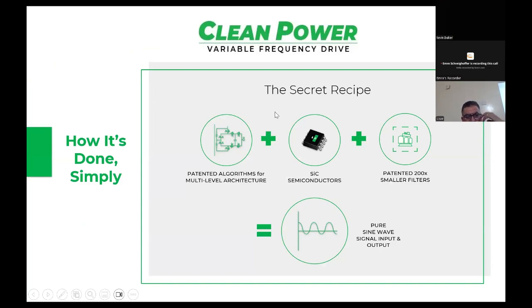So again, just a quick review. The secret recipe is our patented algorithms. We have a multi-level architecture. All VFDs on the market are 2-level; we are 3-level, which is usually a medium voltage design because you can hide the cost of these things in medium voltage, and you never used to be able to do that in low voltage. So we are a true 3-level VFD on both sides, the active front end side as well as the output side, which means we have many more steps, contributing to a true sine wave. We're also using silicon carbide semiconductors and the 200 times smaller filters that are now patented as well. The result is we have a pure sine wave to the motor.